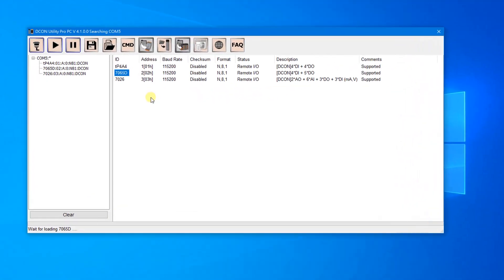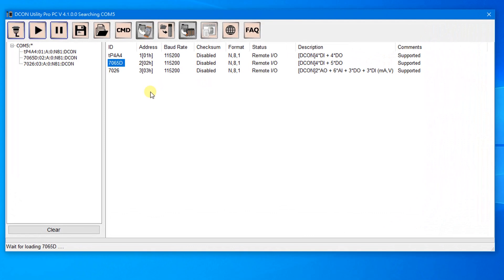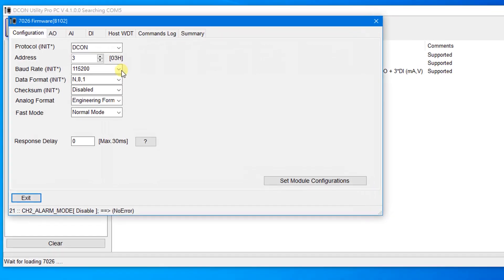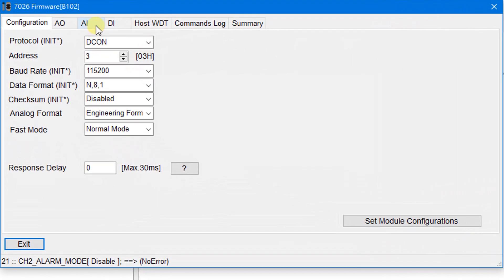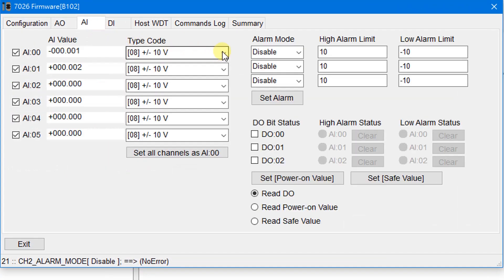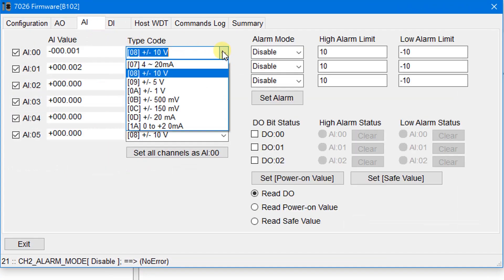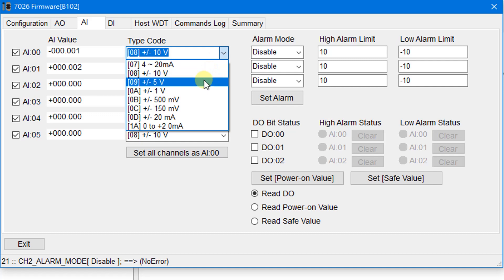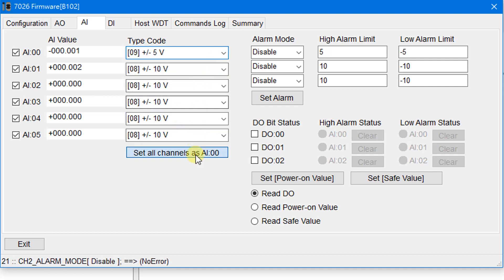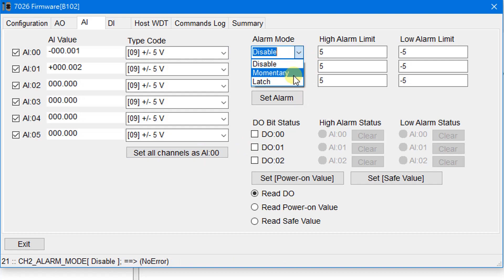Now we will describe how to set and test the alarm function. Open the M7026 setting window. On the AI page, set the type code to ±5 Volts and set all channels as AI0. Set the alarm mode to Momentary and Latch.